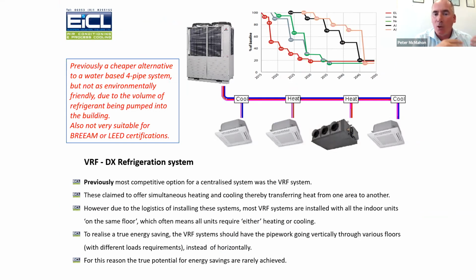Now, I appreciate a lot of you have DX systems, but equally you'll appreciate the cost of refrigerant, especially if any of you have had refrigerant leaks of late. You will know the cost of refrigerant has gone up very, very high. So it's really not as acceptable from an environmental perspective, an ethical perspective, and obviously a cost perspective, to be pumping refrigerant throughout multiple rooms and multiple buildings. So we want to contain that as much as we can. I am on the Institute of Refrigeration, as was mentioned, and we're consistently trying to improve refrigeration systems. One of the best ways we can do that is to reduce the volume of refrigerant. So you can see where we're going with this.